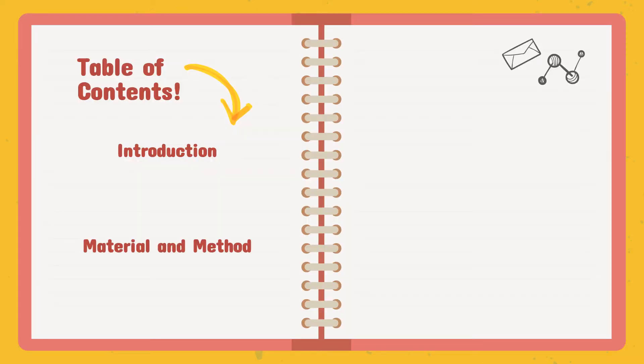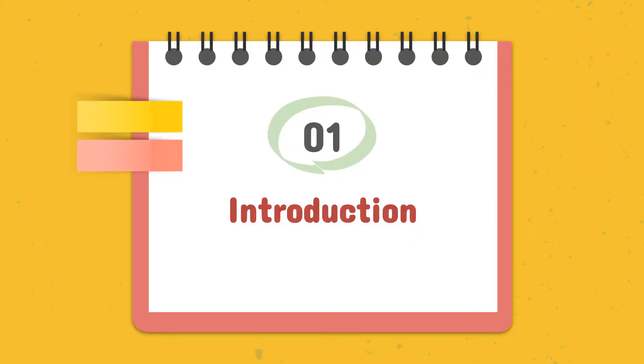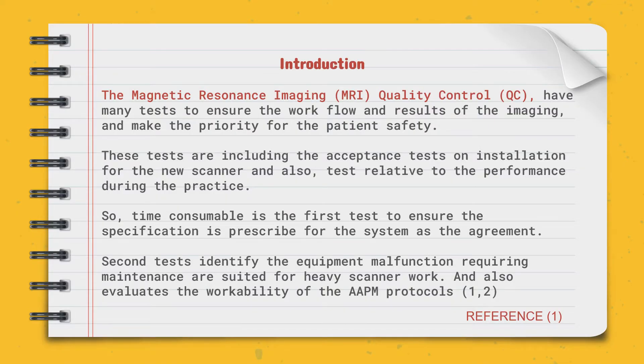The table of contents includes the introduction and the material and method. For quality control, we have many tests to ensure the workflow and result of the imaging and make patient safety a priority. These tests include the acceptance test on installation for a new scanner and relative tests for performance during practice. The first test ensures the specification is prescribed for the system as agreed. The second test identifies equipment malfunction requiring maintenance, suited for heavy scanner work.